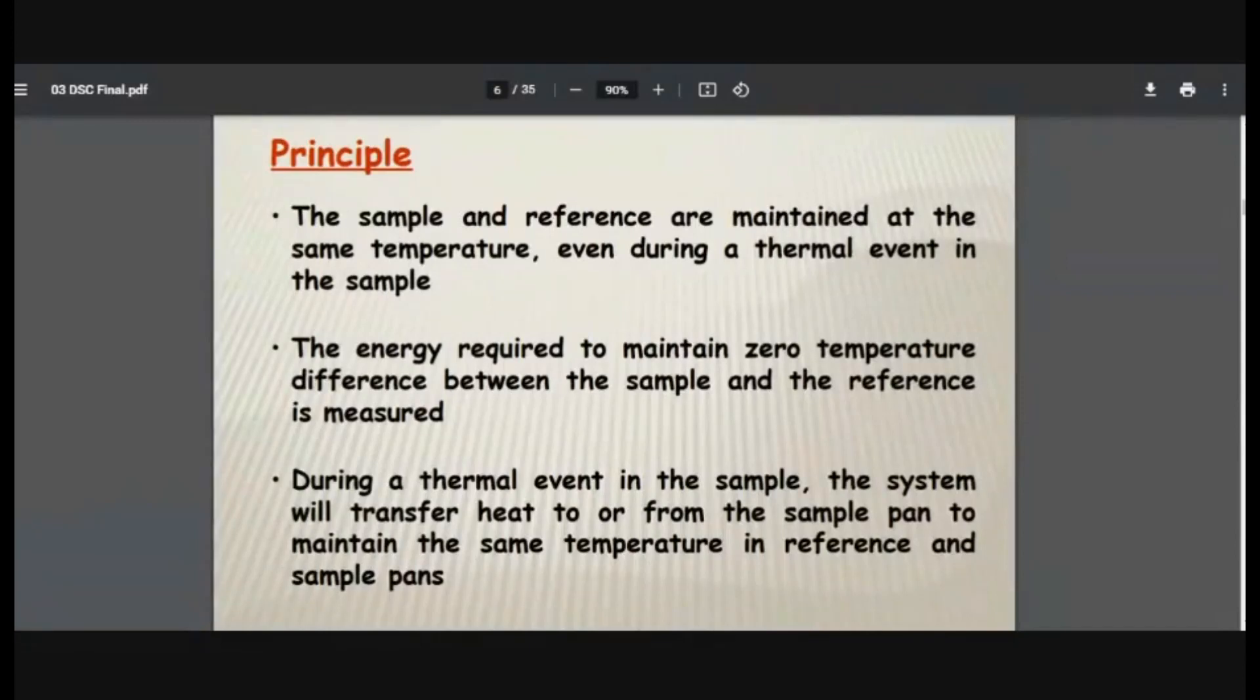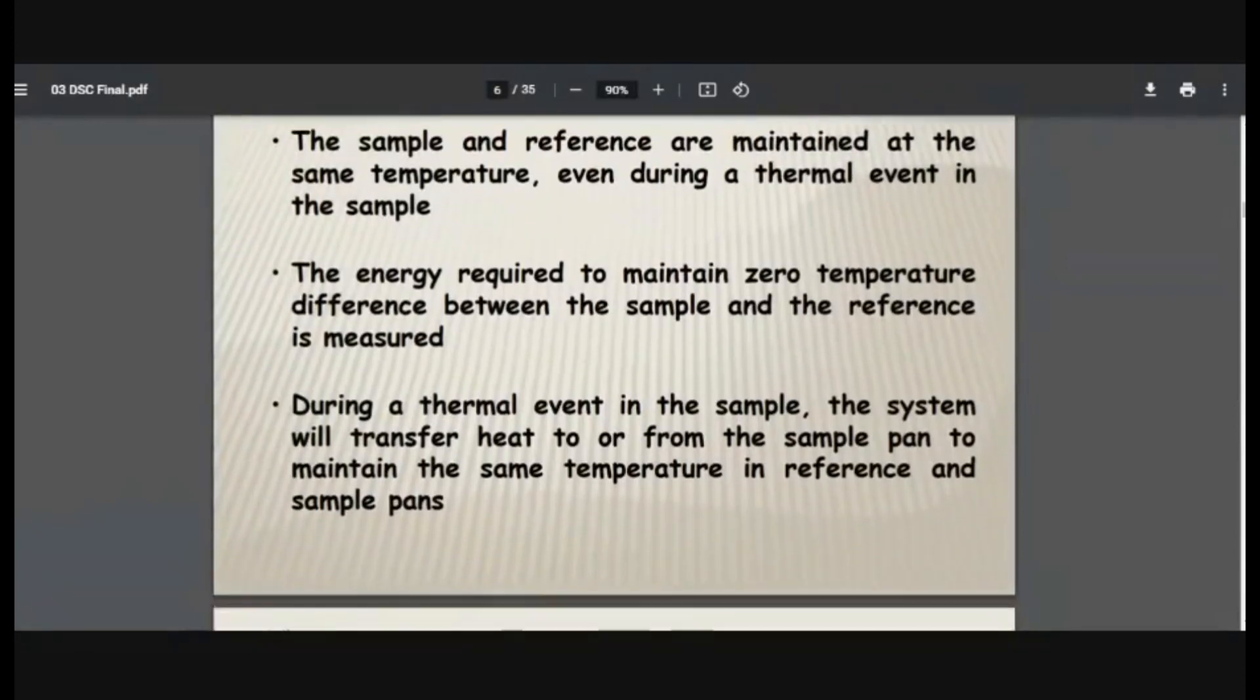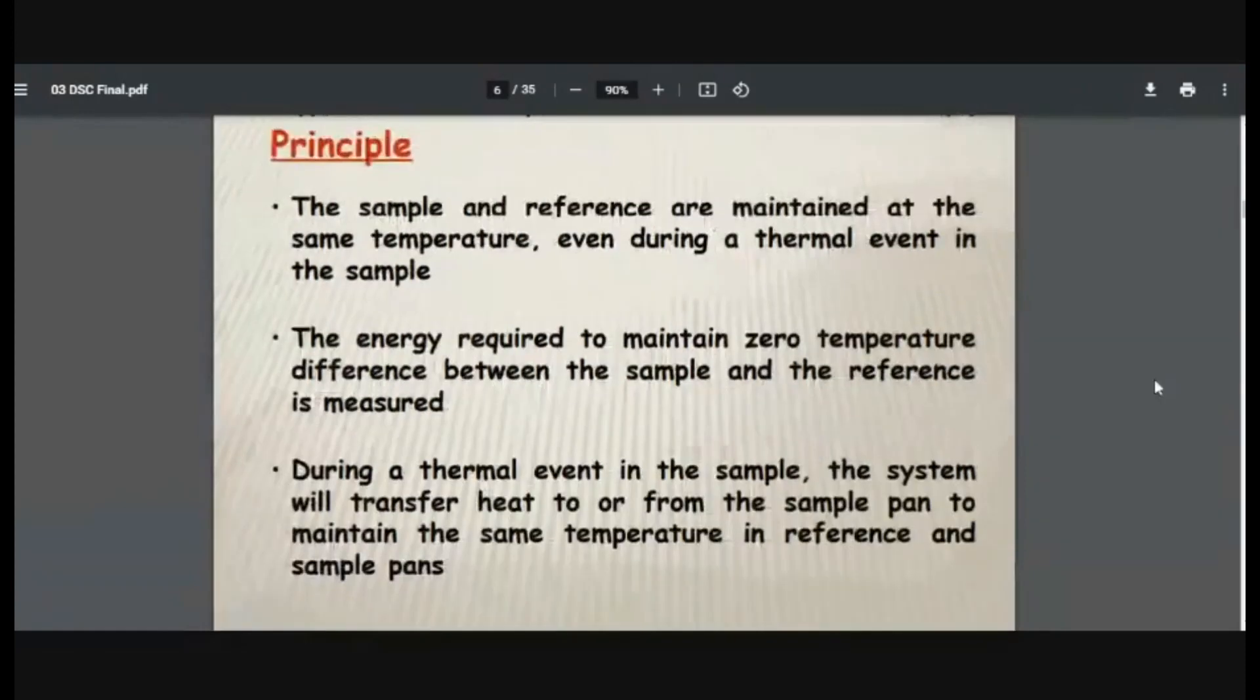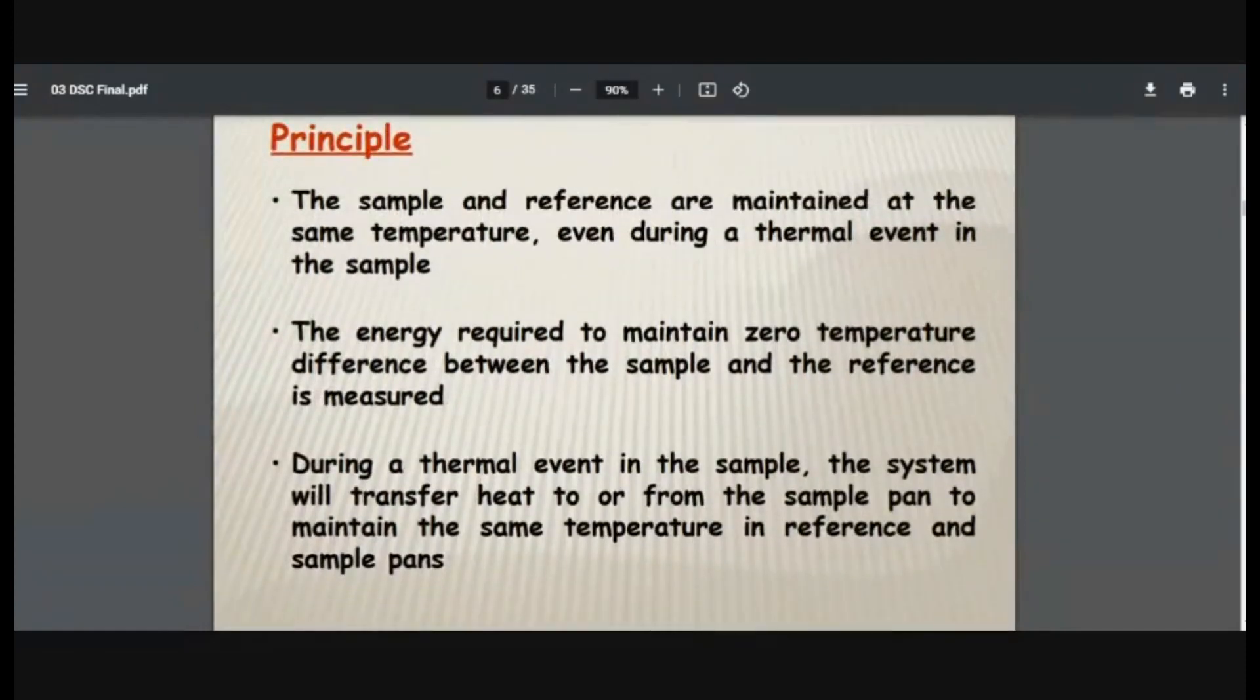Differential scanning calorimetry. The energy required to maintain zero temperature difference between the sample and the reference is measured. During a thermal event like exothermic or endothermic change, so during a thermal event in the sample, the system will transfer heat to or from the sample pan to maintain the same temperature in reference and sample pan. Have you understood all these three points, students? Any doubt?